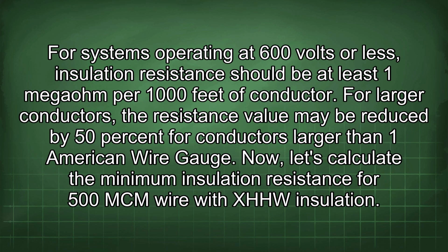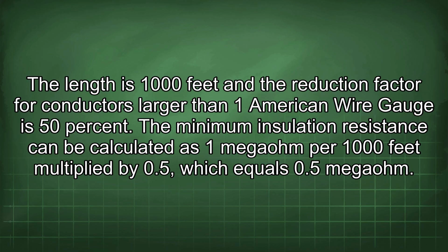For systems operating at 600 volts or less, insulation resistance should be at least 1 megaohm per 1000 feet of conductor. For larger conductors, the resistance value may be reduced by 50% for conductors larger than 1 American wire gauge. Now, let's calculate the minimum insulation resistance for 500 MCM wire with XHHW insulation. The length is 1000 feet and the reduction factor for conductors larger than 1 AWG is 50%. The minimum insulation resistance can be calculated as 1 megaohm per 1000 feet multiplied by 0.5, which equals 0.5 megaohm.